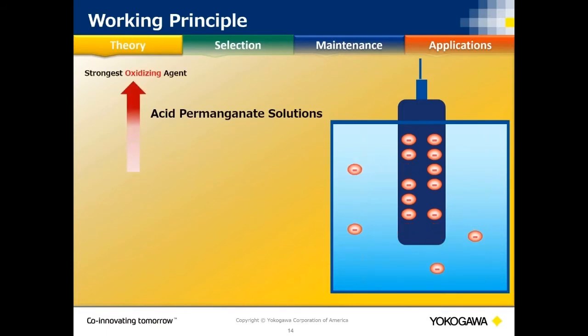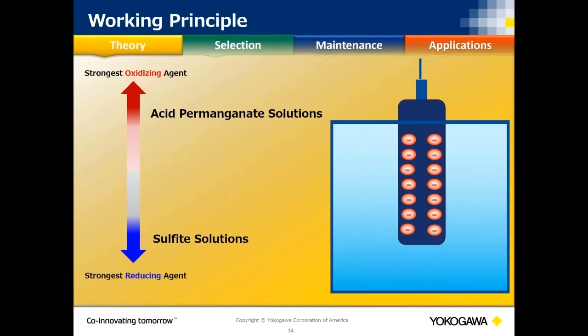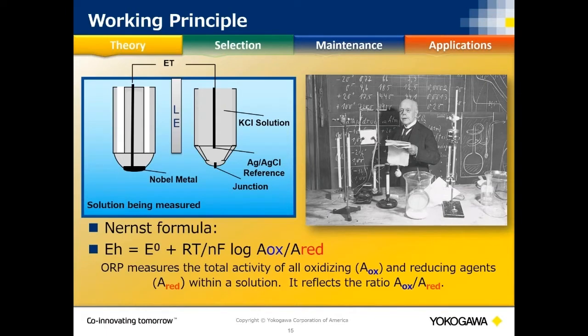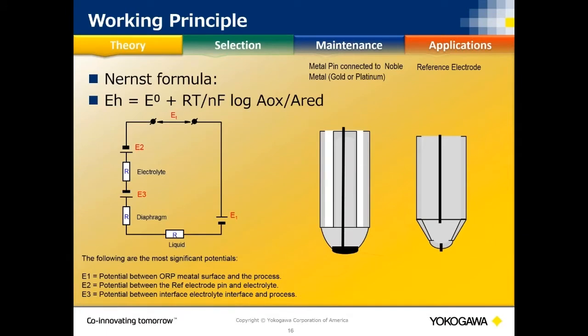Looking at the working principle with an acid permanganate solution: it's strongly oxidizing because it strongly attracts electrons from the redox electrode, so the potential is very highly positive. The opposite — sulfite — is strongly reducing because it pushes electrons into the electrode, giving a strongly negative reading. The calculation all analyzers use is the Nernst equation, the same as with pH, except instead of a pH glass electrode, you're looking at a noble metal and the process's ability to generate a millivoltage on it.